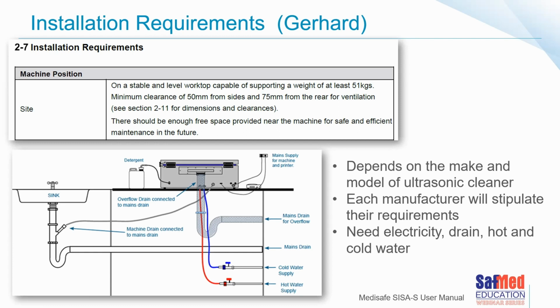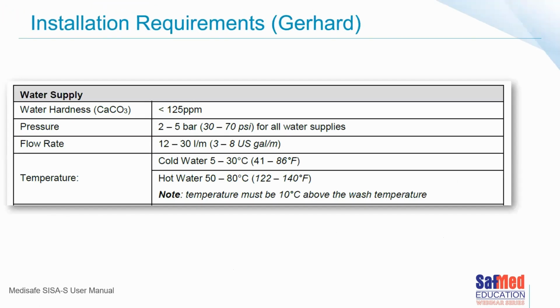point where the machine is plugged into electricity. There might be a printer as well. And then you need a drain for the draining of the machine, as well as an overflow drain. So one would need electricity, drain, hot and cold water, basically as a start-off point, depending on which model you have, a manual or an automatic. Okay, before we go into the next slide, of course, important things like a level worktop surface, one that can support the weight of the piece of equipment, will normally be stipulated, and needless to say, the size. Thank you, Gerhard. Next one.